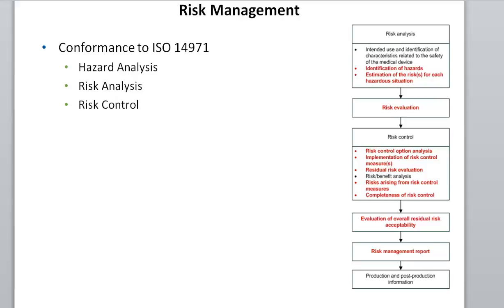If they're in the emergency room or they're unconscious, their ability to detect risk is pretty low. So you can't make any assumption about detectability. So severity and occurrence are two ways that we classify or categorize risk. Then we evaluate whether that risk is acceptable, unacceptable, or needs investigation. There's no specific guideline on what type of severity or occurrence equates to acceptable or unacceptable.